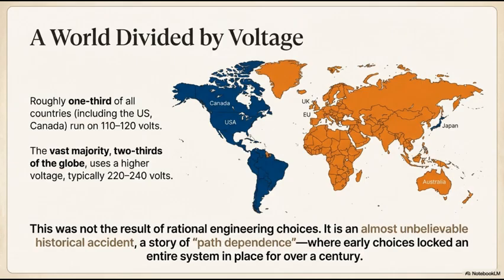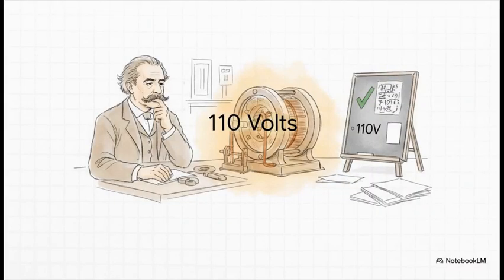We are still talking about the cumulative continuous efficiency costs across the existing pervasive infrastructure, the billions of feet of copper wiring in millions of homes feeding every single standard wall socket. This network runs lights, electronics, small appliances. And while you might argue that the transition to LEDs has shrunk the energy envelope on those 120-volt circuits, that only addresses new loads. The physical infrastructure itself remains optimized for loss. That continuous 75% comparative efficiency penalty, it's an ongoing long-term tax embedded in the widespread 120-volt base.